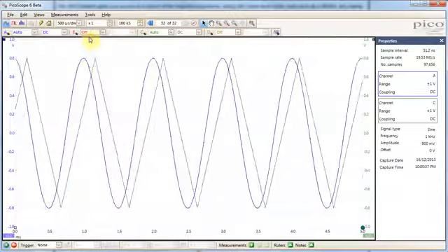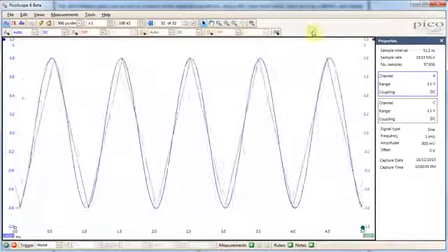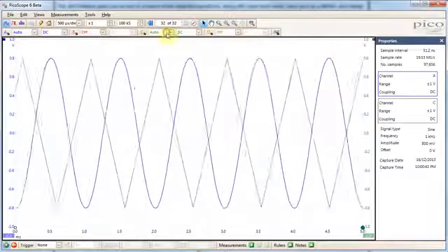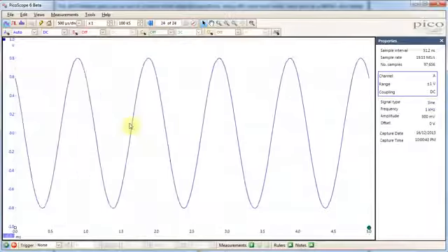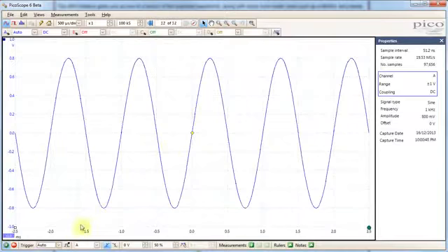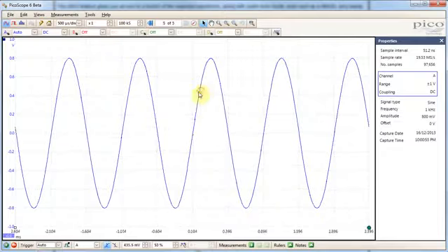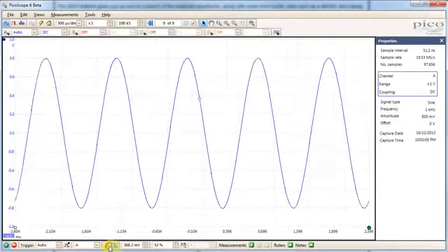Anyway, for the PicoScope, let me switch off all but one channel here. At the bottom is where you set up the trigger, so I can set the trigger to auto, and the real scopes may have this ETS, equivalent time sampling mode there. This is pretty standard. You can switch trigger edge or trigger level, and this gives you the more advanced trigger options.